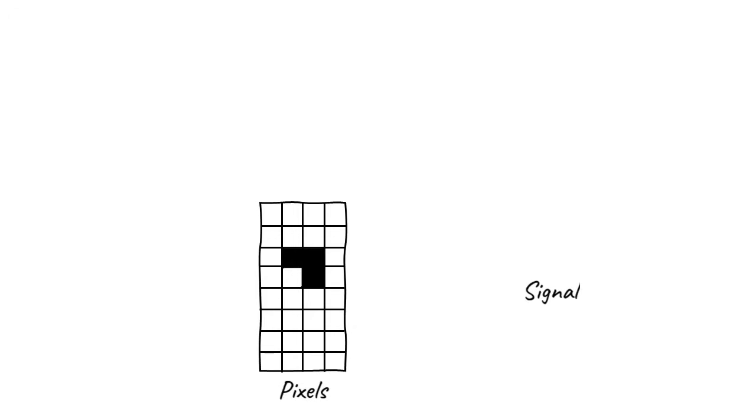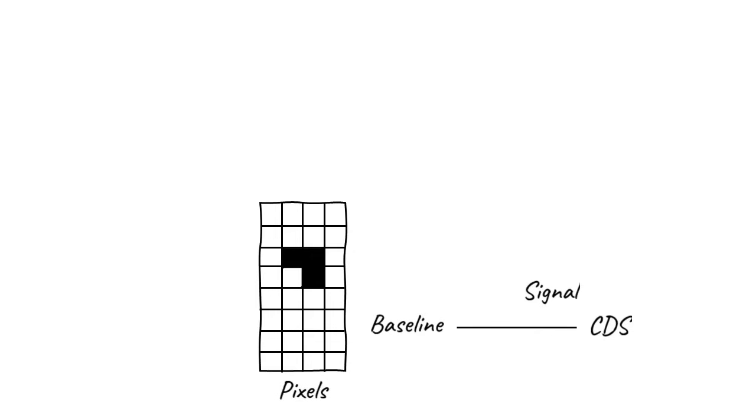Recall that one of the major sources of noise in a CMOS sensor is reset noise, which is addressed by CDS mode. But instead of approximating CDS in software like other cameras, we've built it into the pixel design. On Apollo, the baseline value of every pixel is continually sampled on chip on the timescale of hundreds of microseconds. This ensures that the signal from an incident electron is added on top of a known baseline.